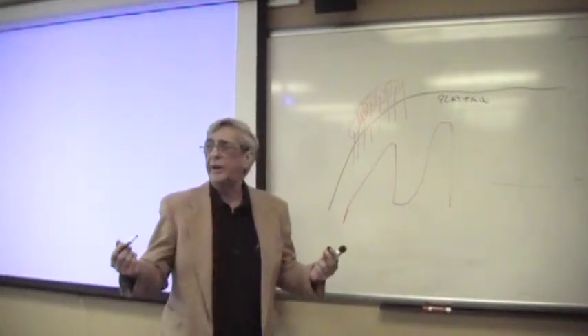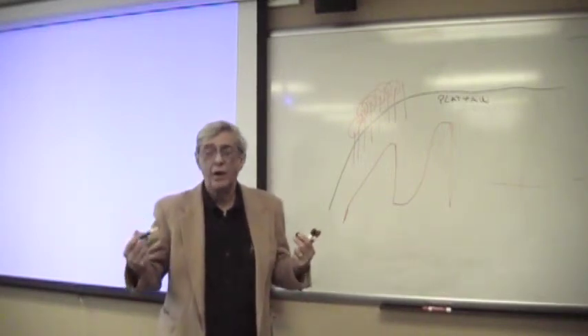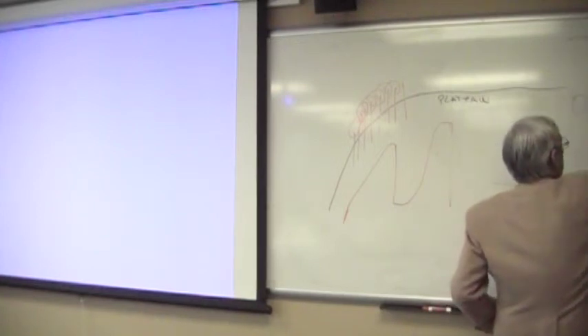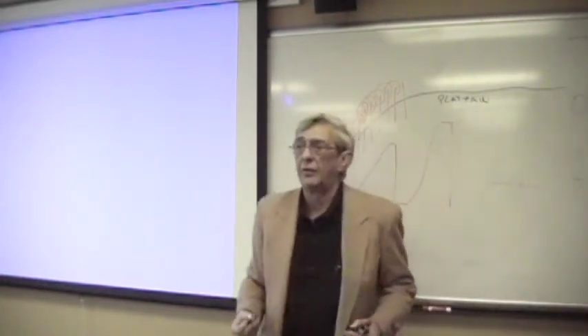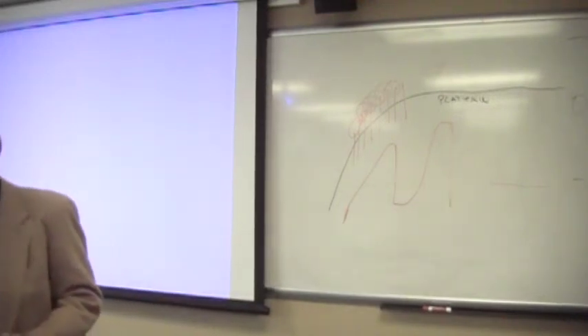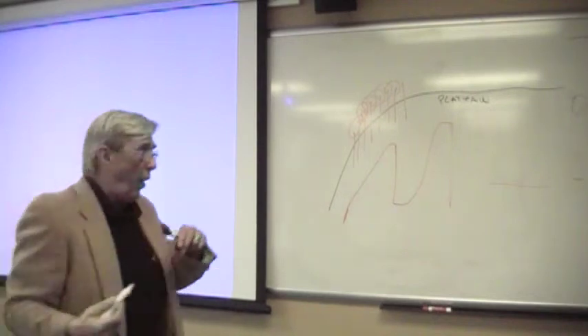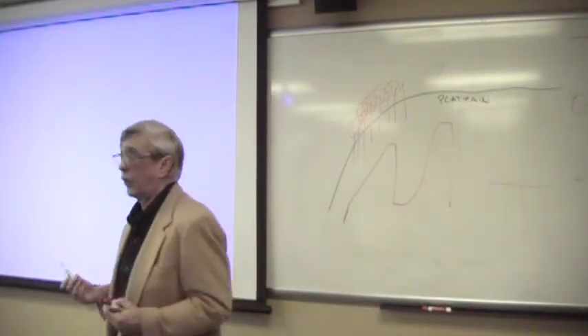So just to be clear, when you have an upward spike like that, it's not going to say invalid sample, it's going to say detector overflow on the ticket. If you actually get raw alcohol, or an alcohol concentration beyond the range of the instrument, which is 0 to 0.6, when you get an alcohol concentration beyond 0.6, you've exceeded the range of the A to D converter and the instrument can't process it. There's nothing it can do except say detector overflow, because to the instrument it looks like you've just dumped a whole bunch of crap in the sample chamber. That's what it looks like.